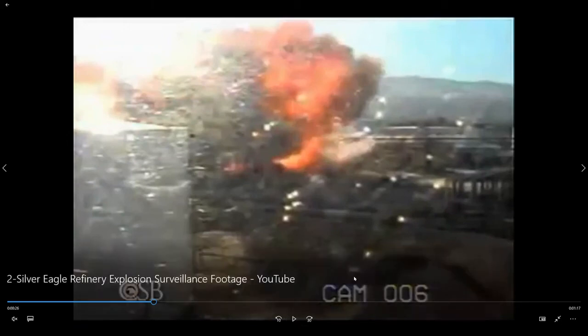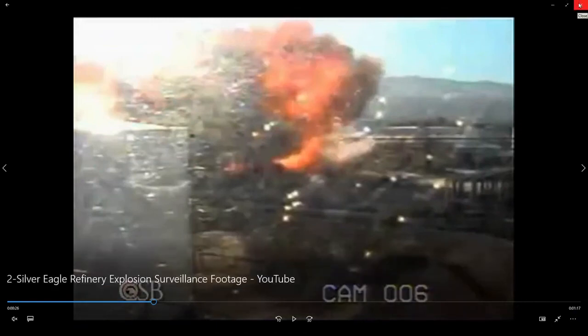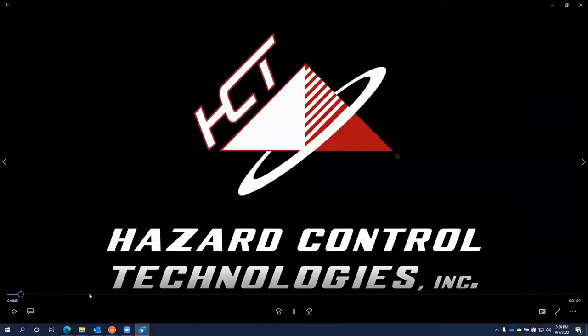And I'm saying, hey, we can detect the vapor leak. We have fire panels that can send that signal back saying we have a vapor leak here, and that can send a signal to the operator - let's shut down zone 3. In the meantime, we can engage the fire pump, which can proportion in some of the F-500 encapsulator agent, and we can encapsulate this vapor, rendering it non-flammable, non-ignitable, and non-explosive. Everything existed except the spherical micelle, except the F-500. Now that we have the F-500, we're like, why do we have to wait for these explosions?